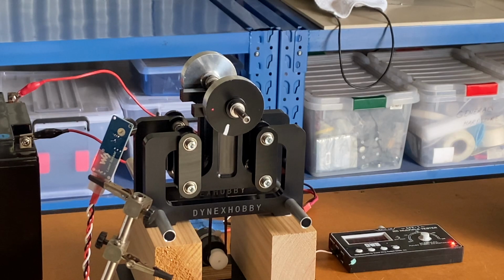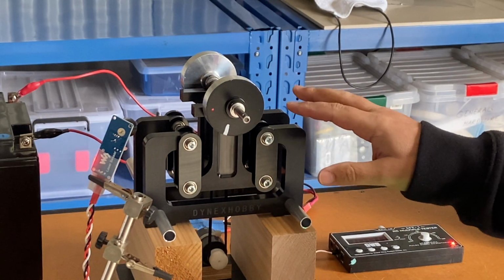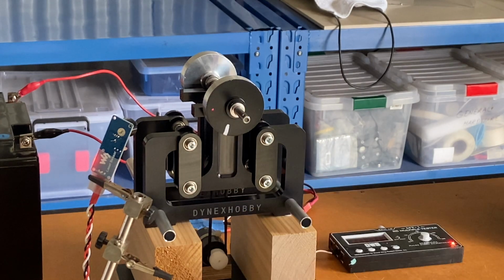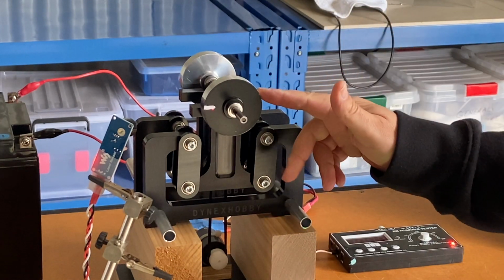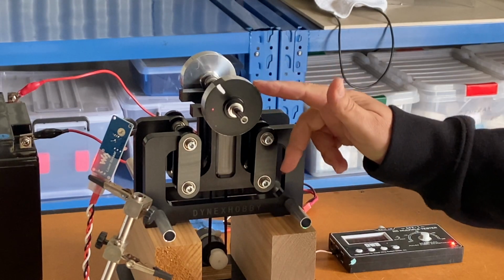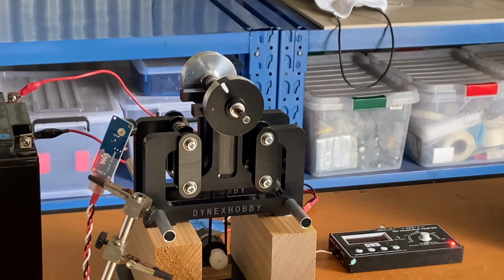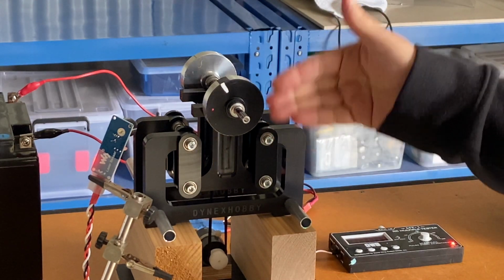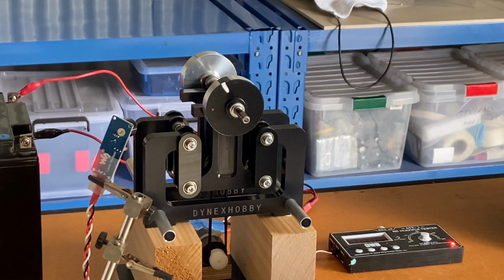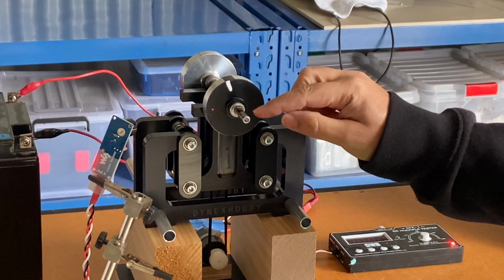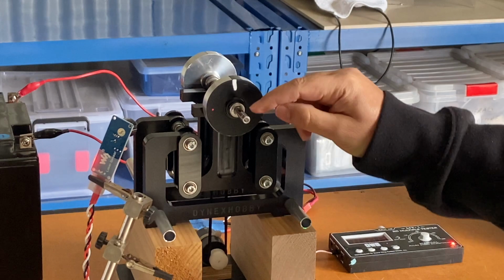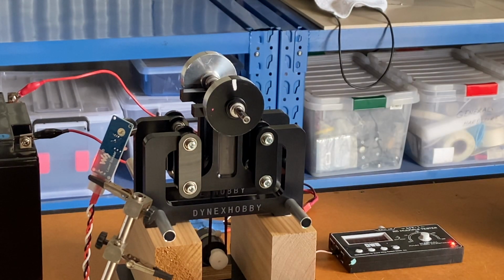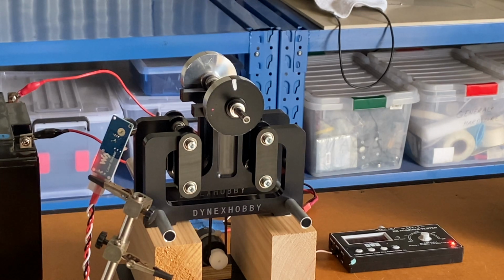So I have my two-plane rotor system set up on the bench, and I have my laser module pointing towards plane one. Now on plane one, I've actually got a couple of different variations of markings on here. So I've got a dark face with a white line marked on it. And I've also got a black marker, which is placed onto the shaft. And I've tried tests in different locations to see which gives me the best results. So I'll go through that and demonstrate some of the pitfalls associated with setting this up.